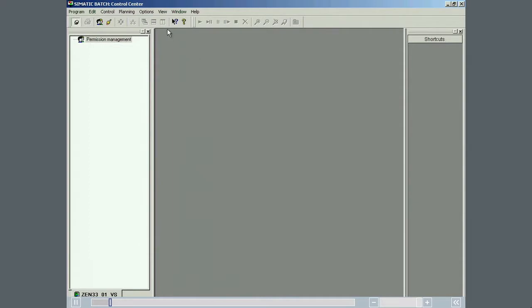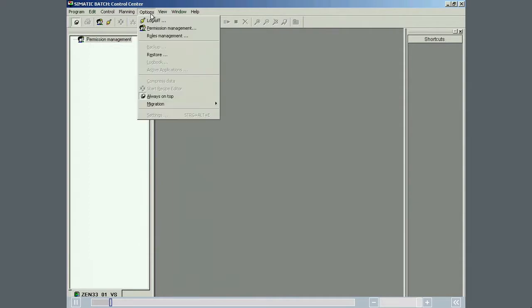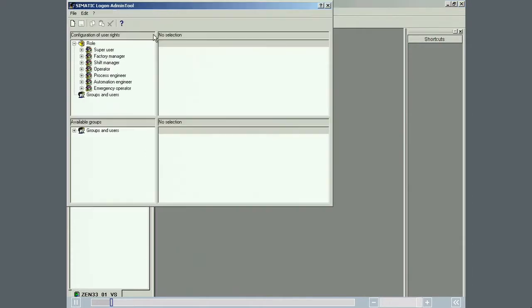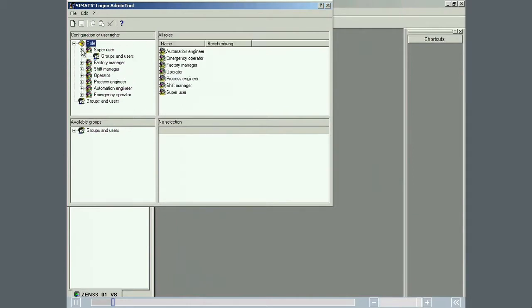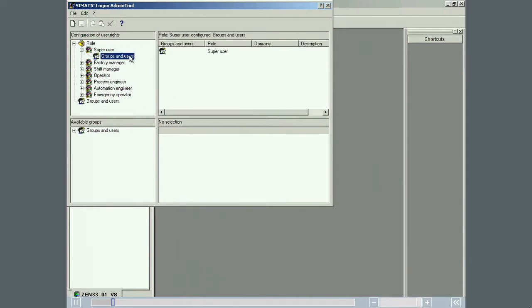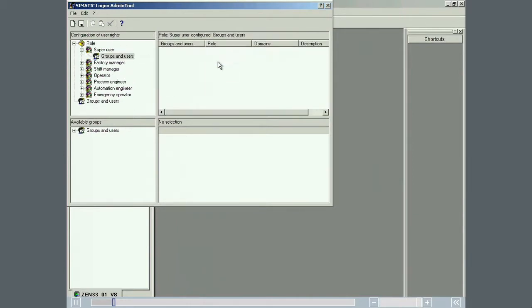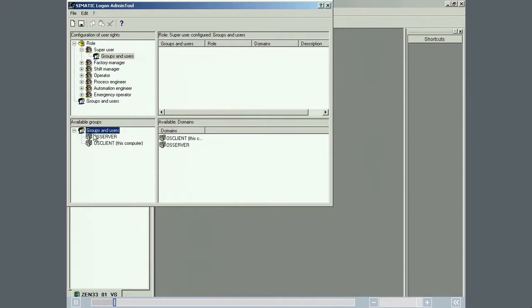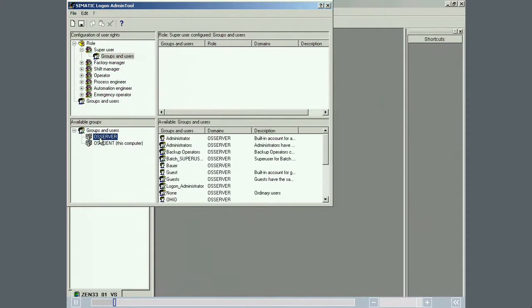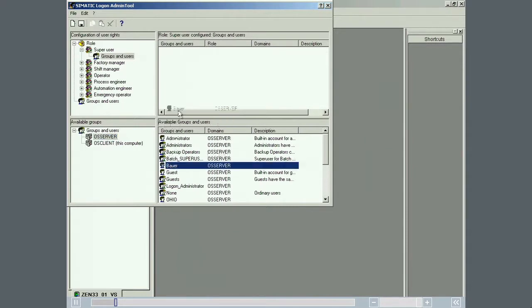In Simatic Batch, this is achieved by defining roles for which specific operator options are enabled and assigning Windows user groups to these roles. In this example, the currently logged on user Mike Bauer is assigned as a member of the super user group. Mike is also a member of the Windows logon administrator group and is therefore authorized to make this assignment.